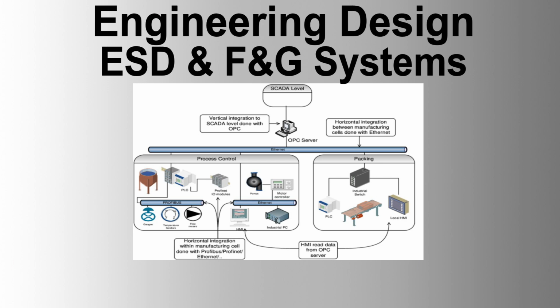2. Replacement and repair. It shall be possible to replace and repair any faulty system module without degrading the operation of the system. Module replacement shall not require system shutdown or disruption of the scanning process, or freezing of output states. 3. Synchronization. The ESD system shall have a facility for automatic synchronization to the DCS master clock with an accuracy of 10 milliseconds. The synchronization mechanism must be clearly detailed by the vendor.